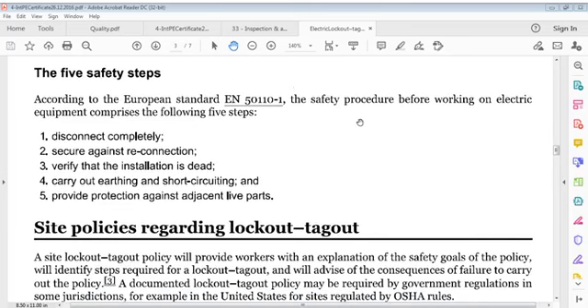Five safety steps that we have to understand. According to European standard EN 50110-1, the safety procedure before working on electric equipment comprises the following five steps. Disconnect completely. Secure against reconnection. Verify that the installation is dead. Carry out earthing and short circuiting and provide protection against adjacent live parts.